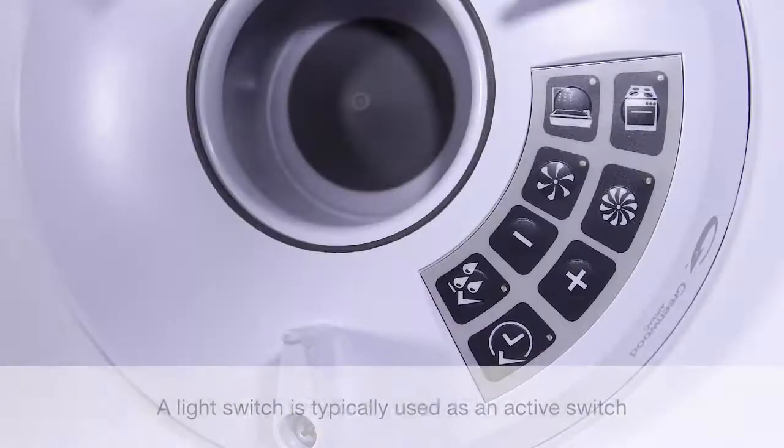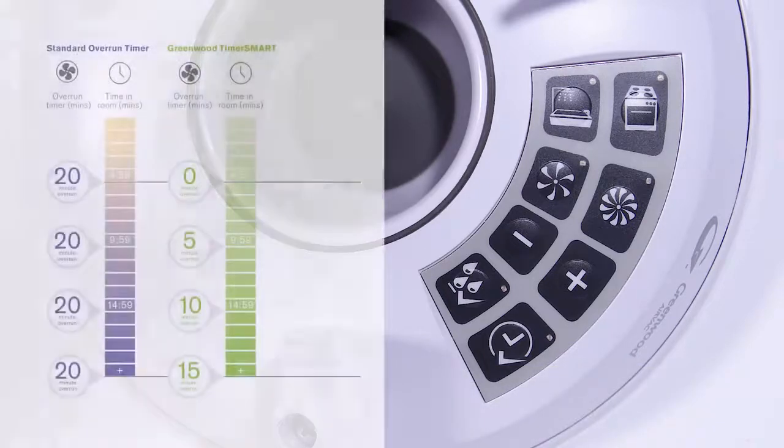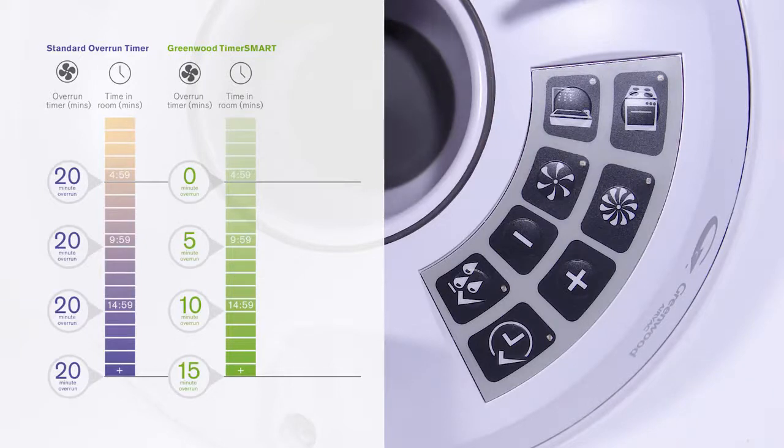The TimerSmart monitors the length of time the unit has been in boost mode via an active switch. Once the switch is deactivated, the TimerSmart overrun period should continue to run the unit for a calculated time in boost. The first five minutes should not activate an overrun.